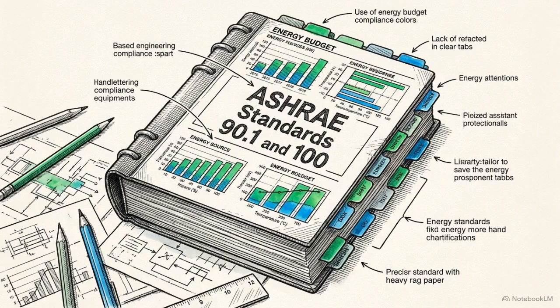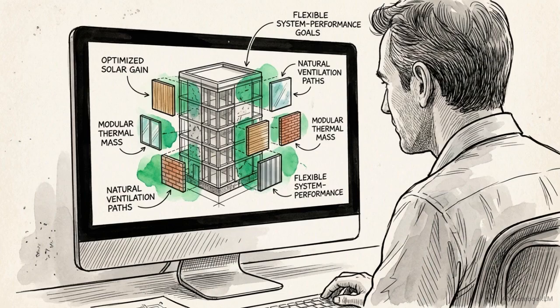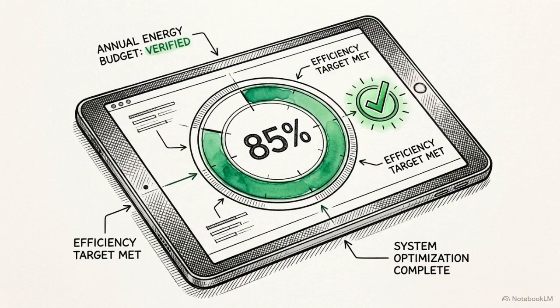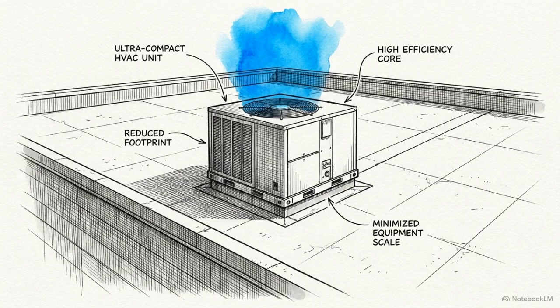To regulate these factors, ASHRAE Standards 90.1 and 100 enforce efficiency by defining an annual building energy budget, calculated in total BTUs per square foot. Instead of relying strictly on prescriptive rules for building materials, these standards provide flexible system performance goals. Engineers can combine innovative materials and systems as long as the total design meets the annual energy budget. A structure with optimized orientation and minimized perimeter exposure requires smaller HVAC equipment, keeping capital costs low and directly reducing operational carbon emissions.